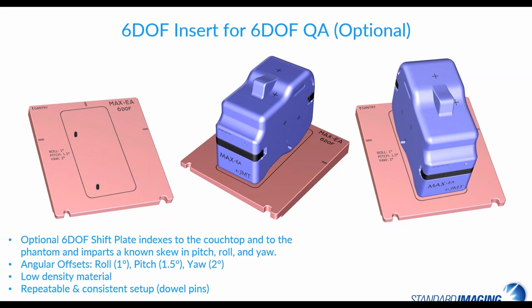So with this, you can quickly put the plate on the couch top and then index your Phantom onto the plate and scan it with the CBCT and see what this shift is, and then allow your 6 DOF couch to correct the shift. So these are the dowel pins.